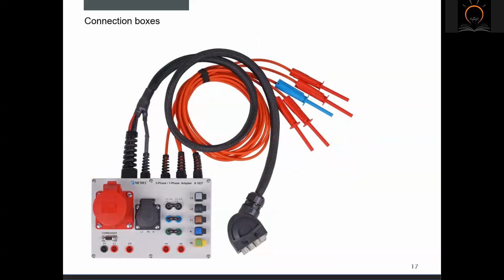The next one in a row is A1627. It is intended for connection of various single-phase and three-phase appliances. But we have to pay attention here. On the three-phase appliances, only passive tests can be executed. So real leakages or power measurements are not supported with this test solution.